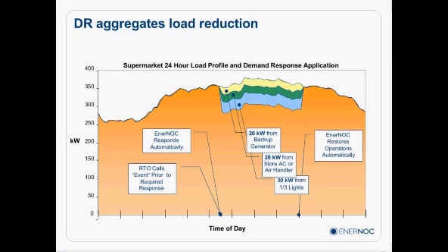This slide is a great demonstration of how curtailment and backup generation can work together to facilitate demand response. This is a very typical grocery store demand response curtailment demonstration. So you can see that an RTO, which is a regional transmission operator, such as ISO New England or PJM, calls an event. This particular facility responds automatically with 3 different types of response. It runs the small backup generator in the back of the facility that powers the front-end registers and servers. You raise air conditioning set points a few degrees, and you also reduce the lighting. That combined response reduces load at this facility by about 15%. It's all done remotely, and at the end of the event, the load is restored automatically.